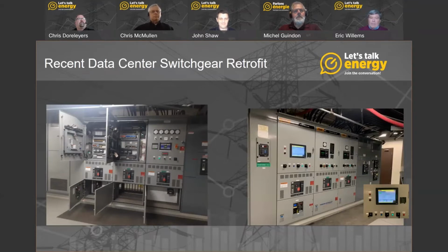The photo on the left shows the paralleling switchgear prior to the retrofit. I direct your attention to the closed door with the 5 meters on the top. The generator controller is a large square panel in the center of the door. To avoid nuisance alarms ringing into the main control room, the alarm conditions were not reset, and the red LED alarm lights on the generator control panels were left on all the time. A full audit was performed.